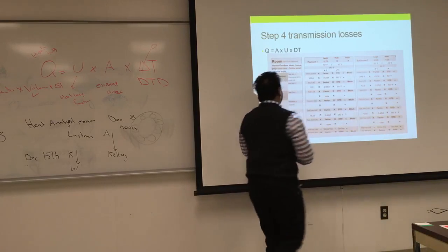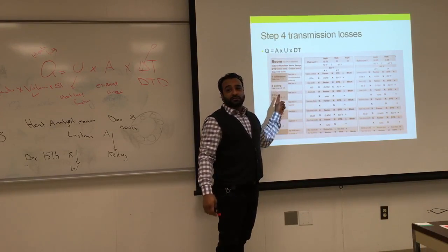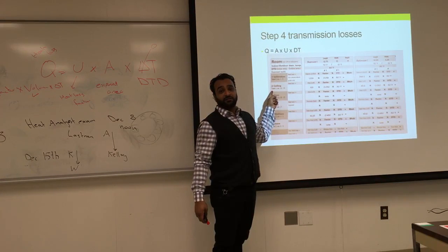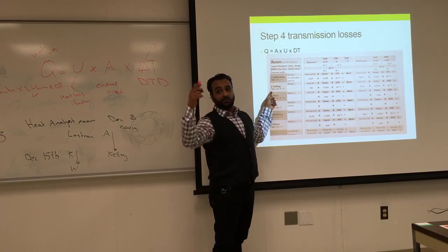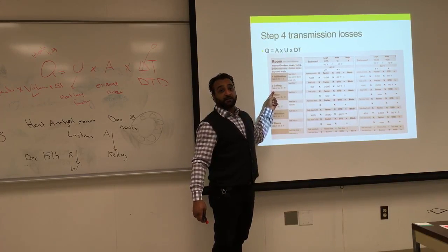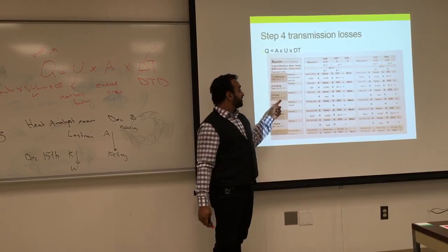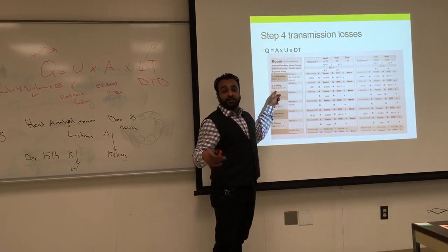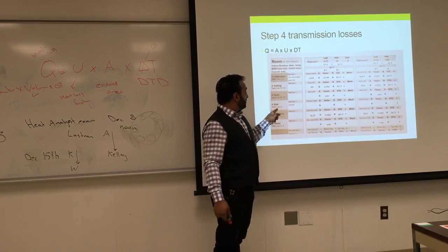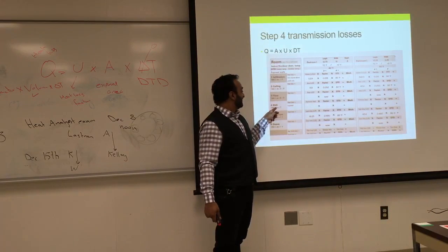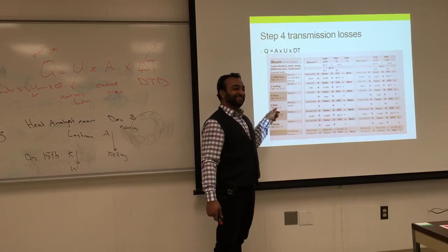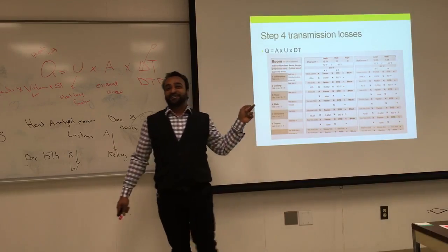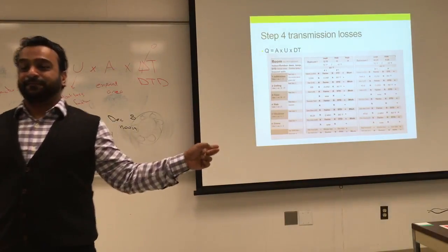This is for a ceiling. Let's talk a little bit about ceiling. So if the floor on top of you is heated, do you consider the ceiling? No. So there's no heat loss to the ceiling. If it's an unheated attic, you will consider the ceiling. Floor, same concept. Those are going to be the same area, and depend whether it's heated or unheated. Slab is different. What's different about slab?